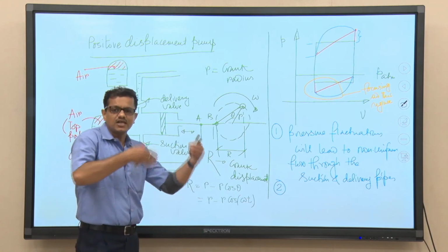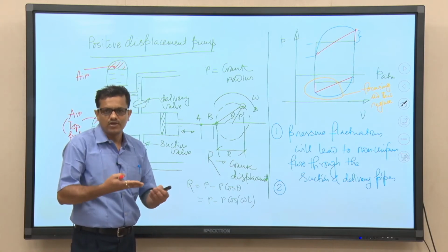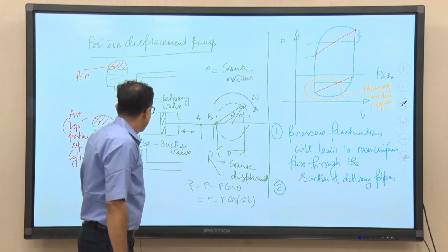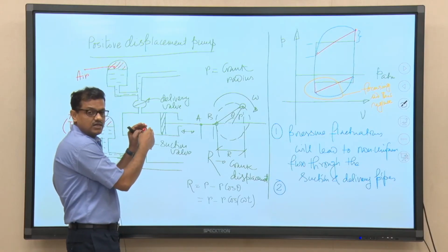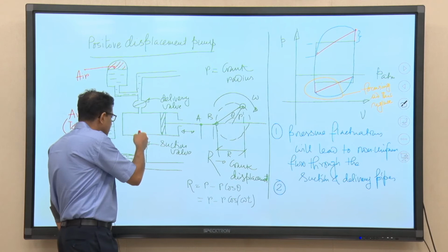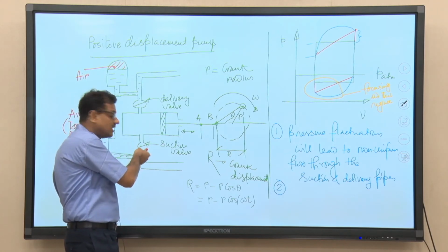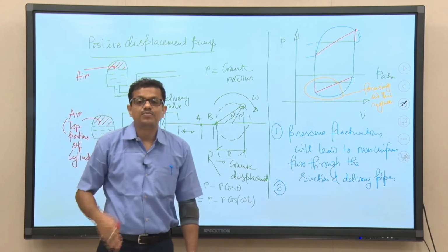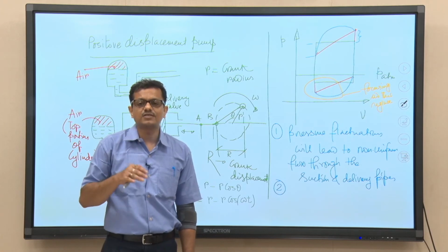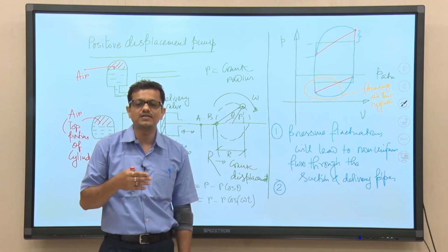So, the higher the pressure drop inside the cylinder, the more is the driving force and the more will be the flow velocity, right. So, when pressure falls inside the cylinder, that information will eventually be transmitted to the suction pipeline. If pressure in the suction pipeline falls below the vapor pressure at the corresponding temperature, we have discussed in greater detail that separation or cavitation will occur.